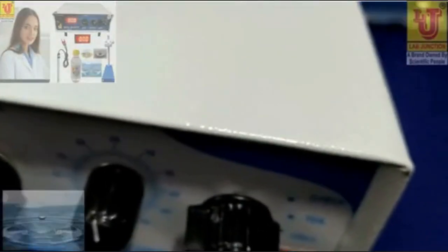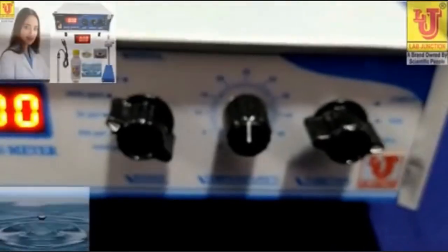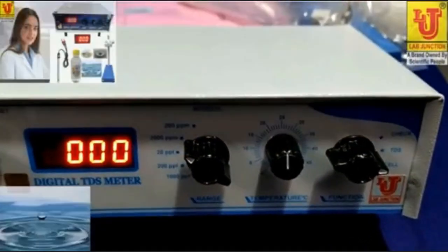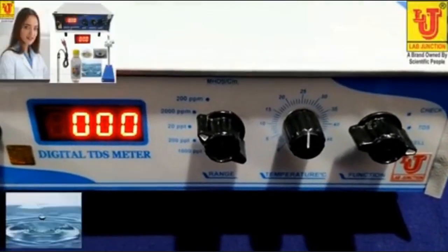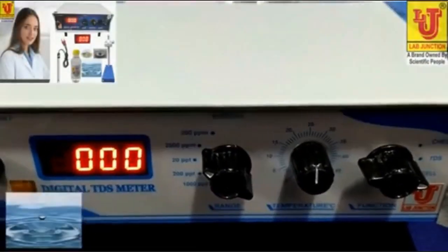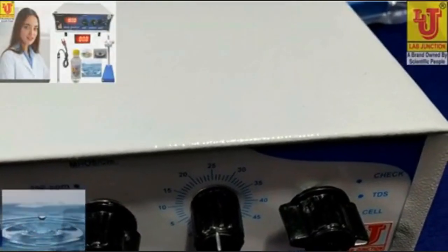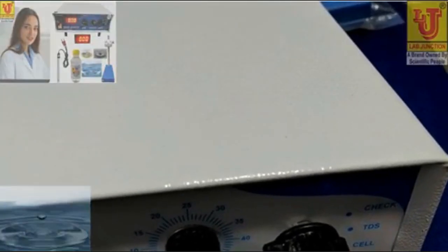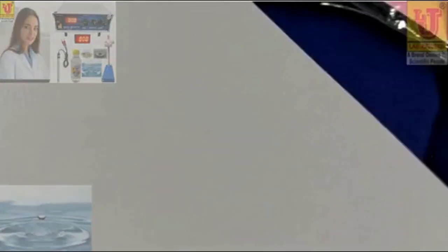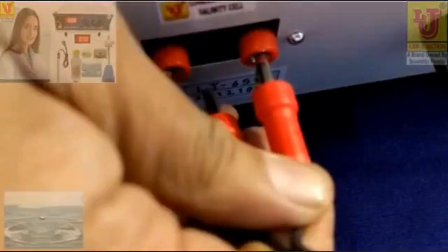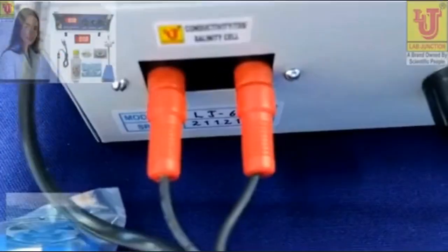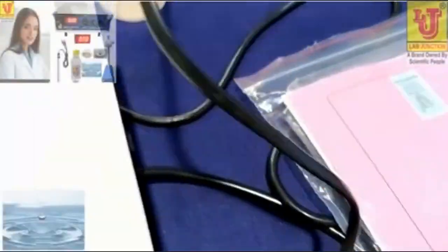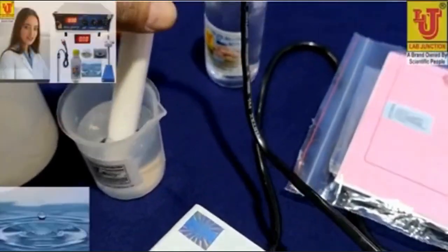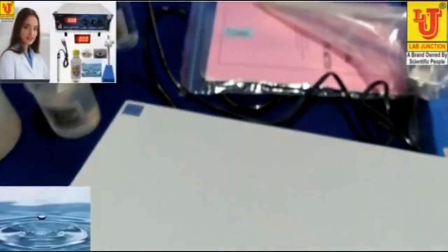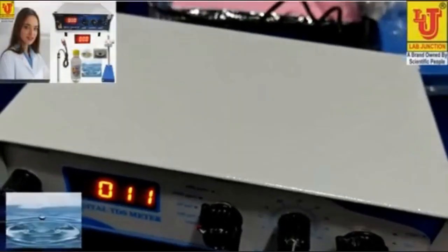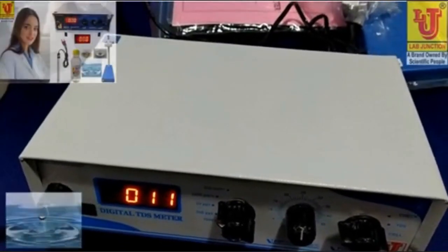Now, how to standardize this digital TDS meter and how can we use it? Now I am connecting TDS cell to this TDS meter. You just plug this in and dip in distilled water before half an hour of testing schedule.